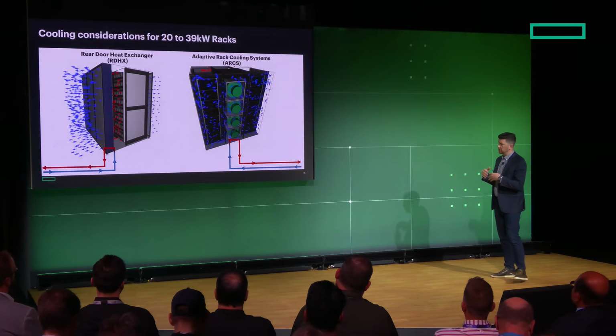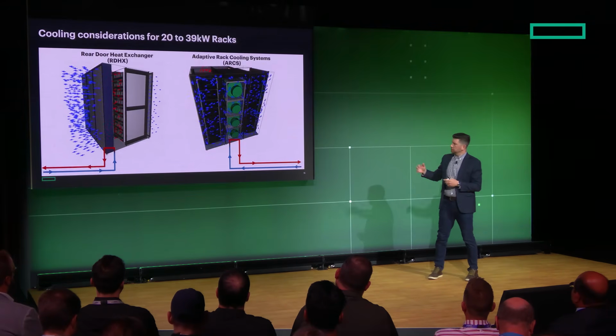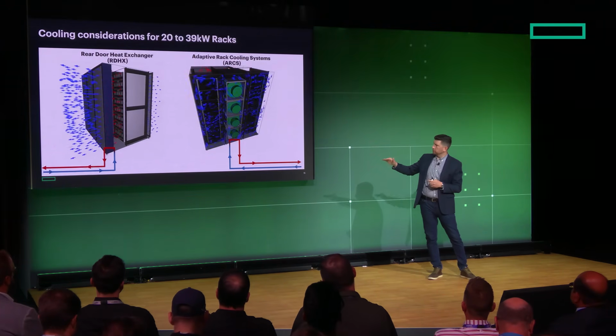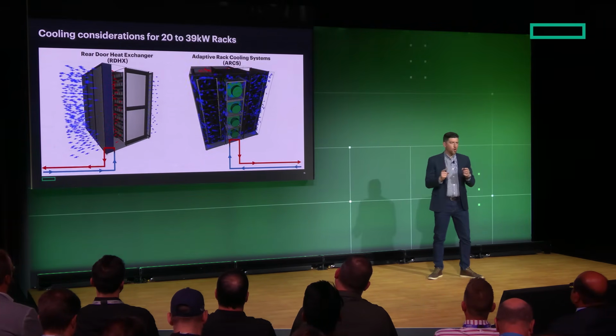Now ARCS is one step further. We're still pumping this cool water directly into the coil, but instead ARCS actually creates that cool air on the inlet side for the servers to suck in, pushes all of that hot air through the coil, and then sucks it back into the ARCS. This is actually a completely enclosed infrastructure that can scale up to 4 racks, using liquid.